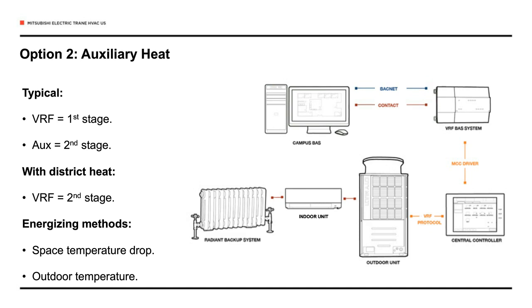Most commonly, we see the VRF as the first stage of heat, and then the auxiliary or backup heat will end up being the second stage of heat, just for efficiency reasons. You want to run the system in the most cost-effective manner, and usually this is the most cost-effective order in which to do the heating. Sometimes in larger cities, we do see district heating, maybe district steam heating or district hot water heating. And in that case, we do have the opportunity and the ability to run VRF as the second stage of heat and the district heat as the first stage of heat.